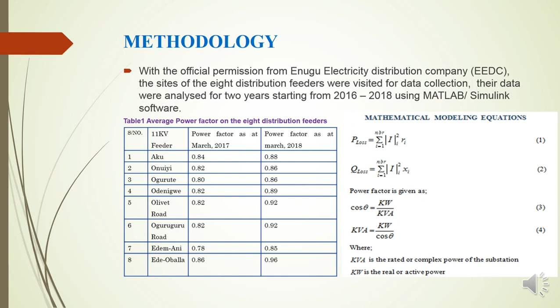Equation 1 helps us to derive the active power loss in the network. Equation 2 provided us with the reactive power loss equation. Power factor corrections were achieved using equations 3 and 4, where the kVA is regarded as the complex power of the substations, and kW is our real or active power. Data analysis of Aku-Nsukka distribution feeder. This model is a single line diagram of our case study, modeled in MATLAB Simulink software. It is an 11 kV distribution network containing 20 buses. These 20 buses show the actual location of each substation along the distribution.